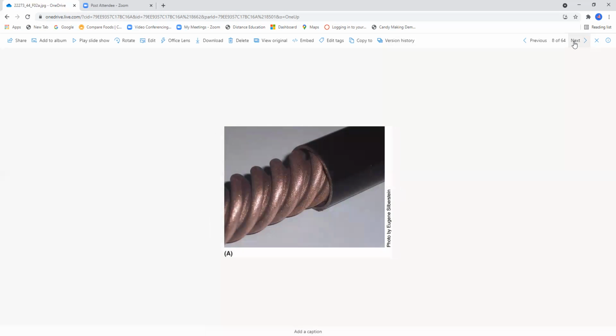Okay, in the same figure 44.2 on page 1327, a cutaway of the coaxial cable, which we talked about in the slide presentation. This is basically a tube within a tube heat exchanger. The refrigerant flows in the outer tube while the water flows in the inner tube. So basically what we're doing here is creating what we call a counterflow refrigeration effect. In other words, we're going to maximize heat transfer because the refrigerant flows one way and the water flows the other way. The ideal beauty of this whole idea is it maximizes heat transfer.